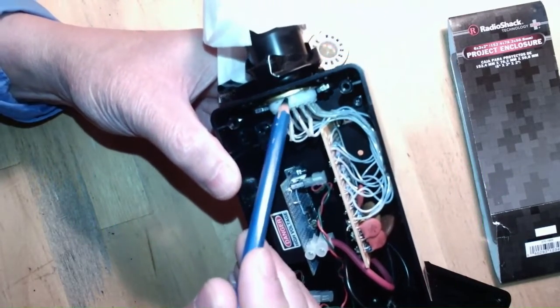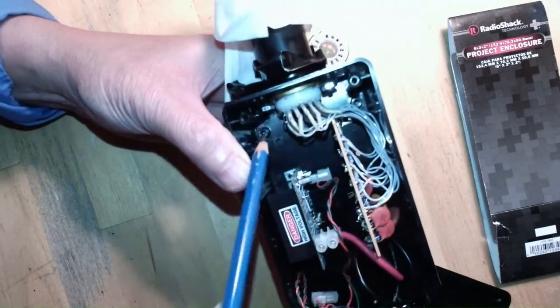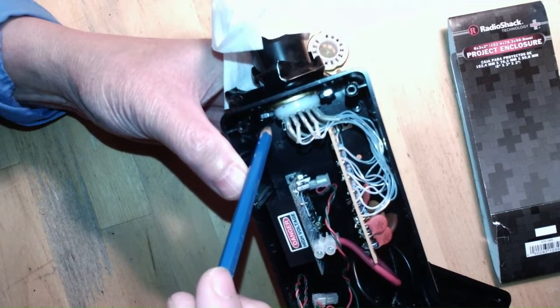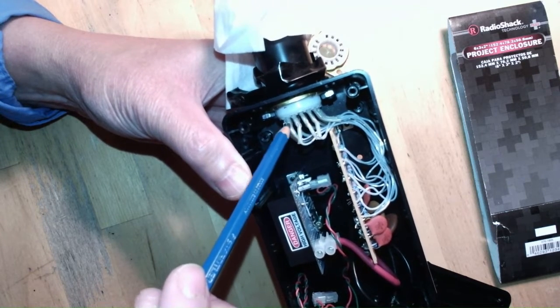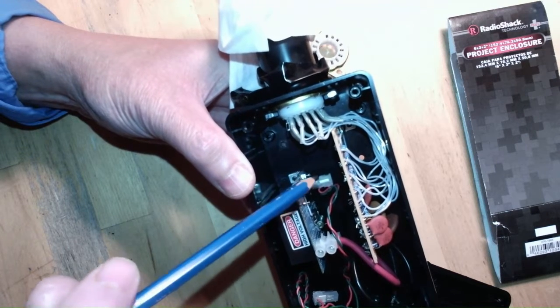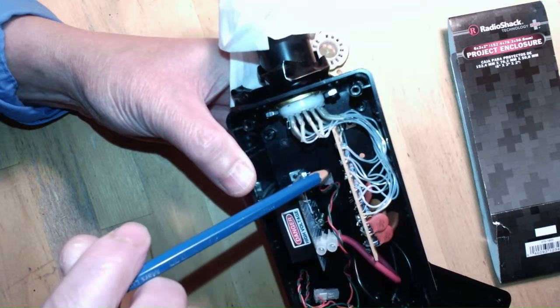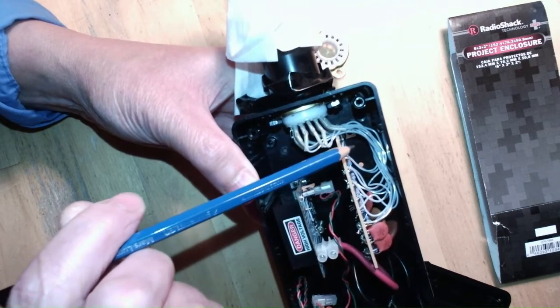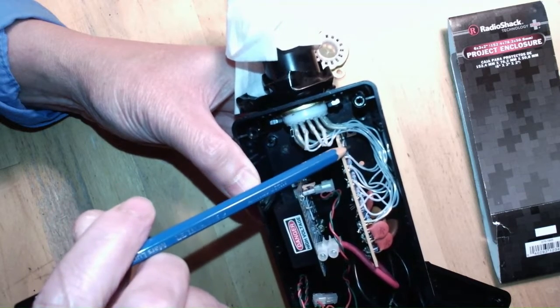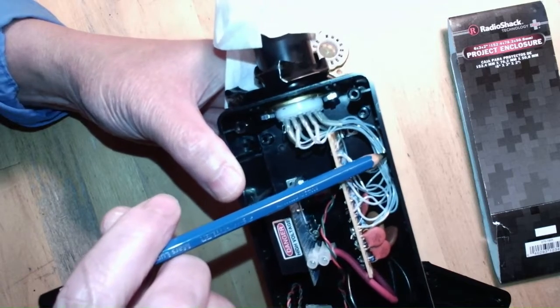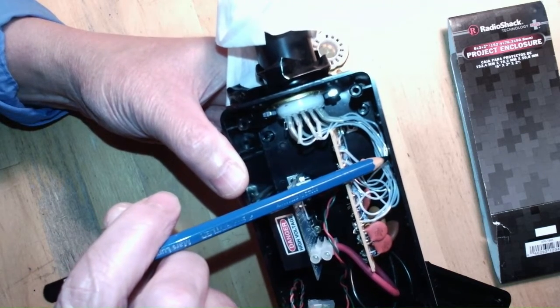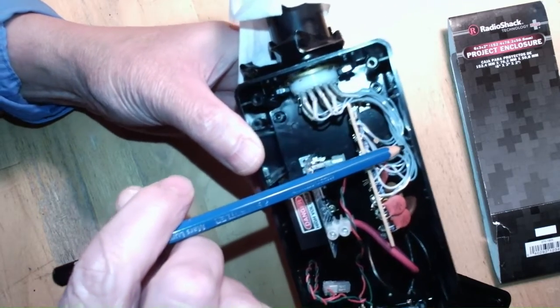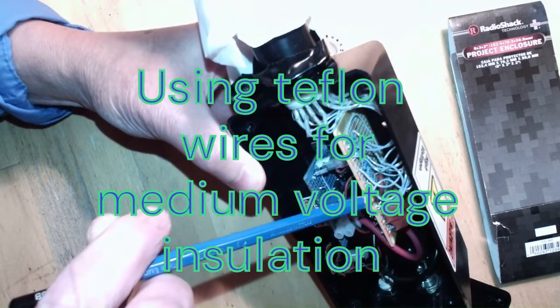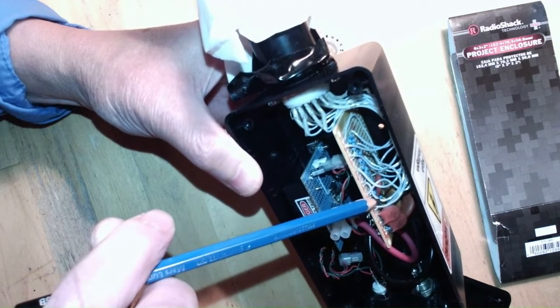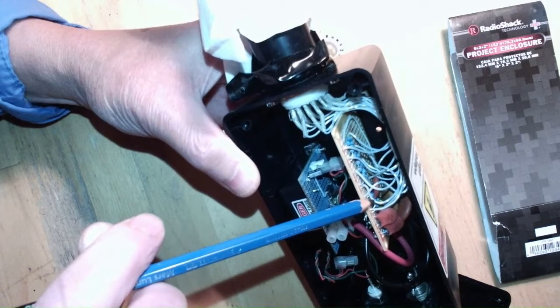And this is the photomultiplier socket. It connects to the photomultiplier detector here. All of this is the wiring from the socket to the various dynode stages on the detector itself. This is the circuit board for the voltage divider, and you can see all these wires here. They connect to the various dynode stages on the photomultiplier detector. These wires are not your ordinary wires. They are actually Teflon wires. We also have the resistors. Here you can see the resistors, and these are from Digi-Key. They have what we call a high voltage tolerance. I think they can hold up to 300 volts.